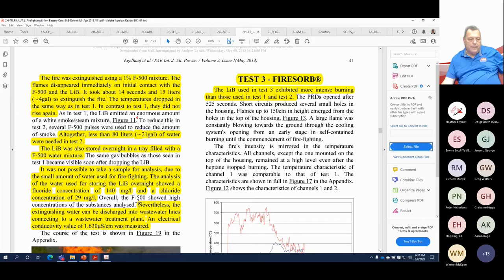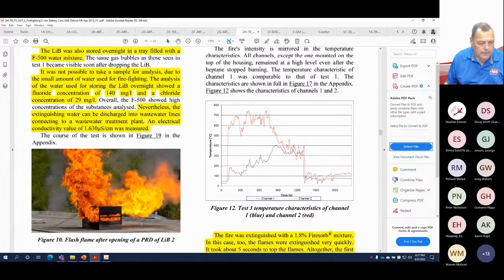But this is one of the big differences between using plain water and using an encapsulator agent. We have 3 separate test reports showing that with the runoff from an encapsulator agent, you're not creating hydrofluoric acid like you are with water. The runoff from an encapsulator agent extinguishment can be diluted down and run through a municipal or industrial wastewater treatment plant. On the other hand, the runoff with water needs to be treated.